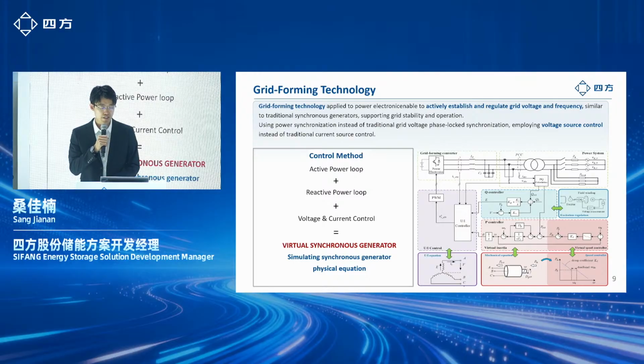We can see from here, grid-forming technology is applied to power electronics to actively establish and regulate grid voltage and frequency, which is similar to a traditional synchronous generator. From the diagram, we simulate the synchronous generator physical equation and add the active power loop, reactive power loop, and the voltage control loop to make it like a virtual synchronous generator.